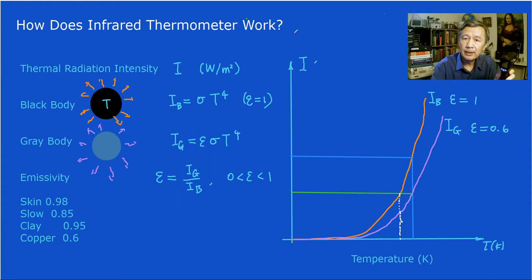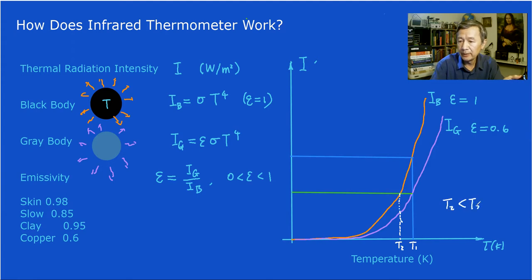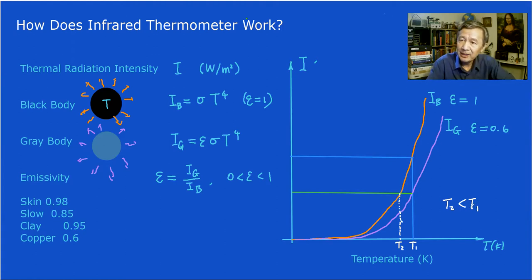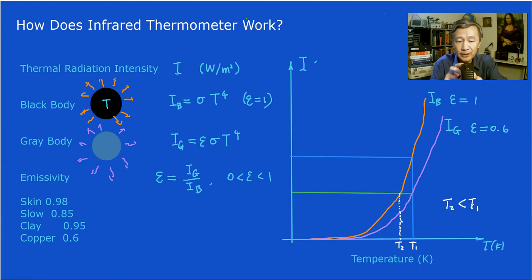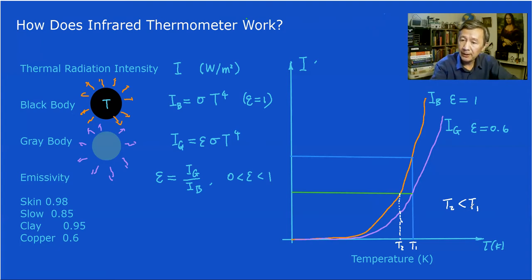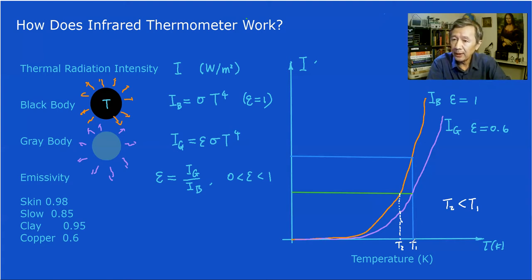If this is the actual temperature T1 and this is the displayed temperature T2, then T2 is lower than T1. That is the problem. If you go to the market and buy an IR thermometer, check whether you can adjust or reset the emissivity. If you cannot, you will always have this trouble — you will obtain readings that are lower than the actual temperature the object has.